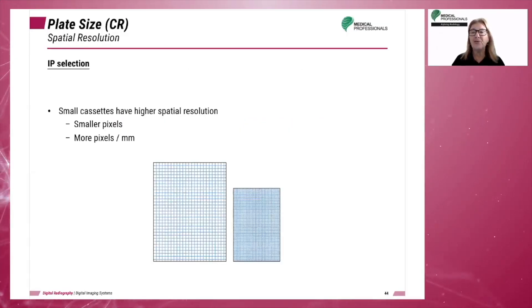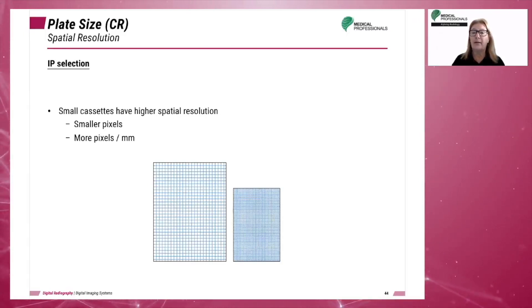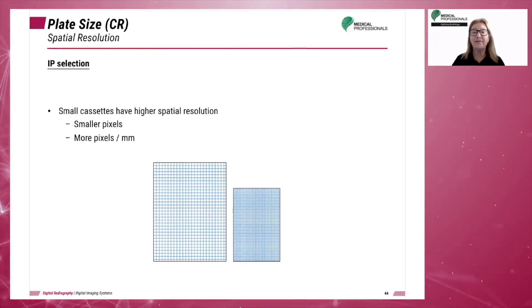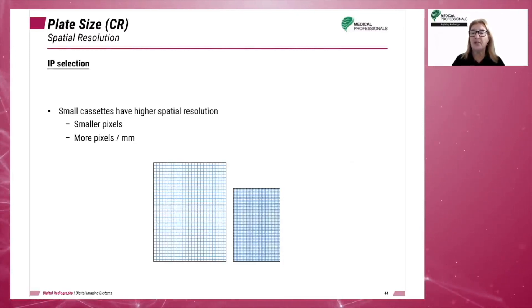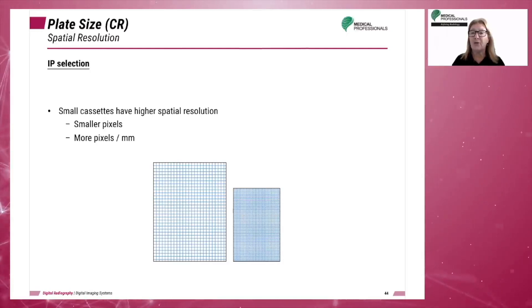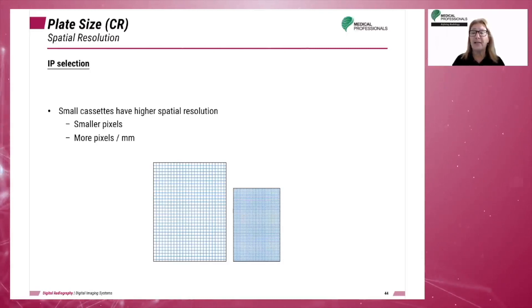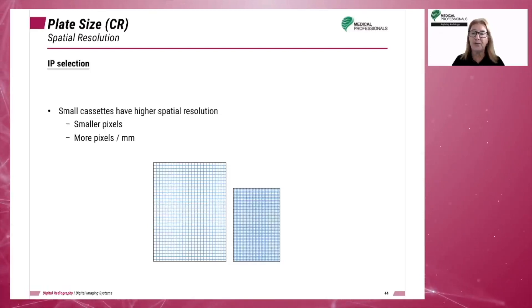Spatial resolution depends on the imaging plate size as well. CR readers scan at a relatively constant frequency of approximately 2,000 by 2,000 pixels. Using the smallest IP possible results in the highest sampling frequency and thus in higher spatial resolution.